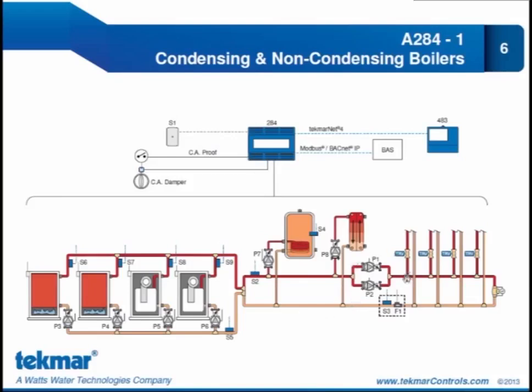How are we proving flow for the primary pump operation? We're doing that with a flow sensor F1. The type of flow sensor that can be connected to the 284 is a 0 to 10 volt analog vortex type flow sensor. And this same flow sensor can be used to provide proof of flow. It can also be used to measure flow, and we can communicate that flow measurement to the building automation system.